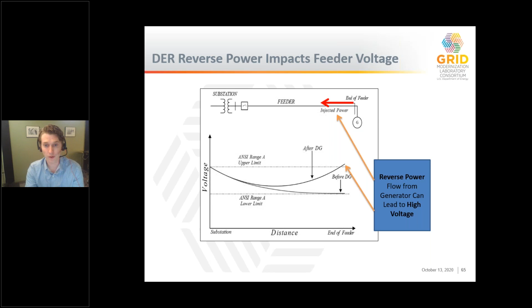The first option is for the DER to consume reactive power. So now we have this opposing effect where the DER is injecting active power and consuming reactive power, and there's a cancellation effect in terms of the voltage rise that can occur. How effective that is really depends on the system characteristics in the area.